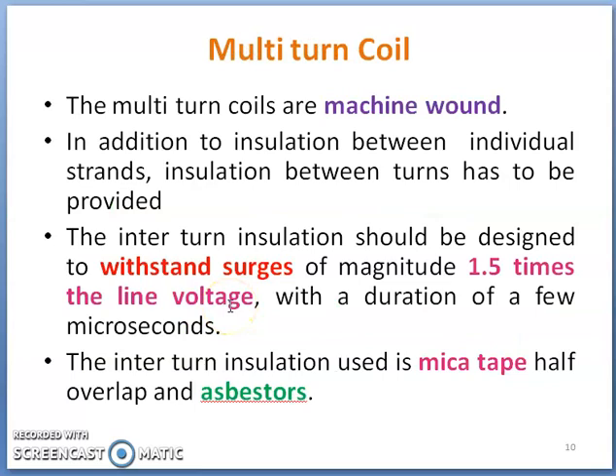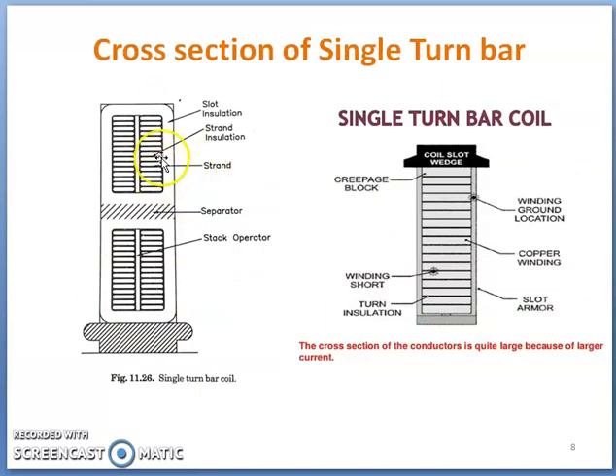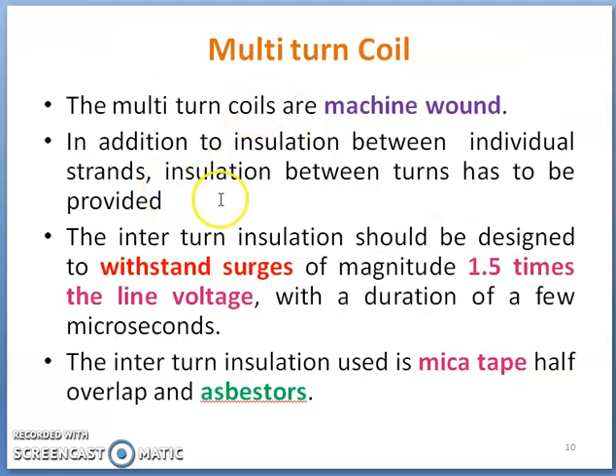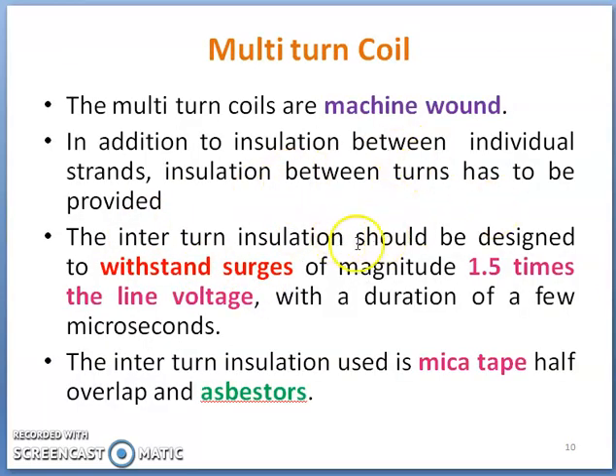Coming to multi-turn coil: multi-turn coils are usually machine-wound. In addition to insulation between individual strands, insulation between turns also has to be provided. In case of single turn coil there is only strand insulation, but in case of multi-turn coil, inter-turn insulation is also required. The thickness of inter-turn insulation is decided by taking into account over-voltage during surges, and it should be designed to withstand surges of magnitude 1.5 times the line voltage with a duration of a few microseconds.